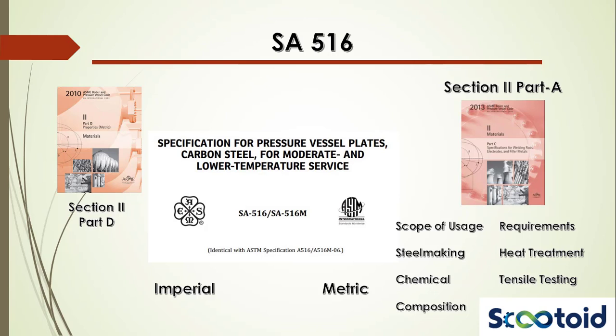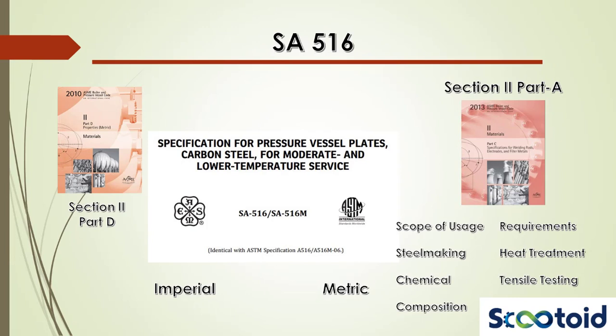In Part D, you'll learn how to read stress tables and learn to determine maximum allowable stresses, minimum tensile and yield strengths, and temperature limits. You'll be exposed to physical properties tables which cover thermal expansion, thermal conductivity, thermal diffusivity and modulus of elasticity. You'll get a brief overview of charts and tables which are useful for thickness calculations. These will be covered in greater detail in the module on Section 8, Division 1.